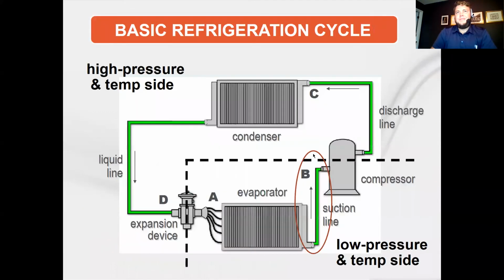Thank you, Marty. Always one for discussion. What Marty mentioned, slugging, is when, where the letter B is, if any drops of liquid refrigerant make it that far, that's a real bad thing, because compressors are meant to handle gas, not liquid. So the purpose of the expansion device, there's two things that aren't shown on that, but the top thing in between the letter D and A, that's a bellows that in a mechanical expansion valve, it senses the temperature and the pressure over at point B.